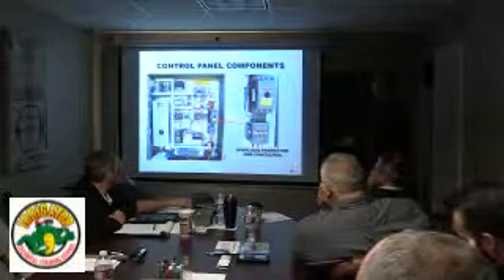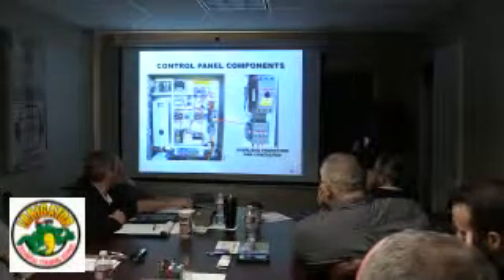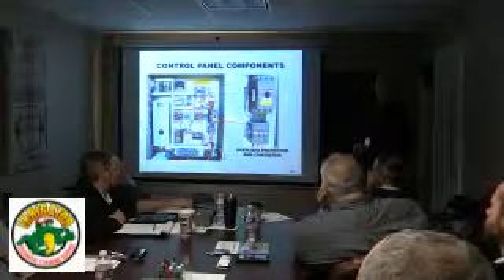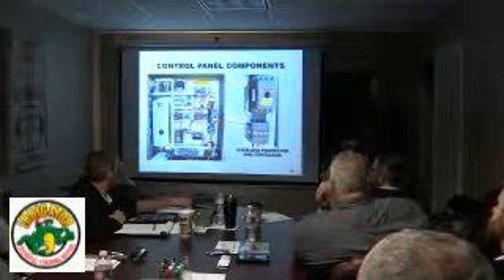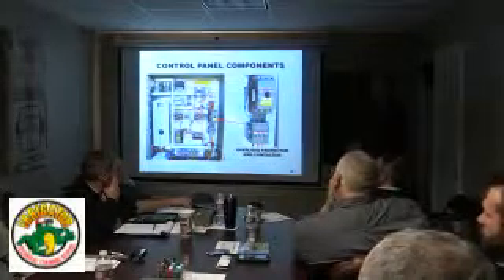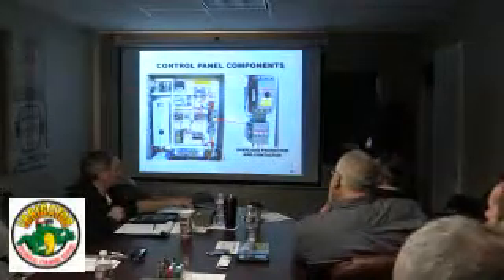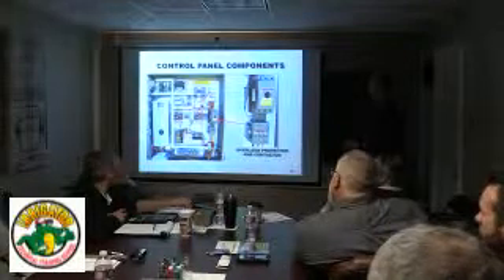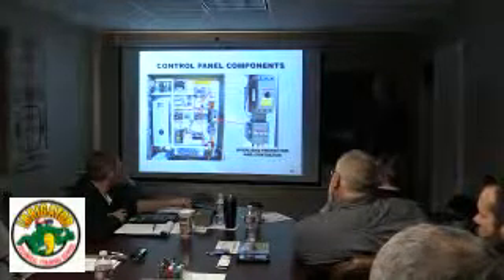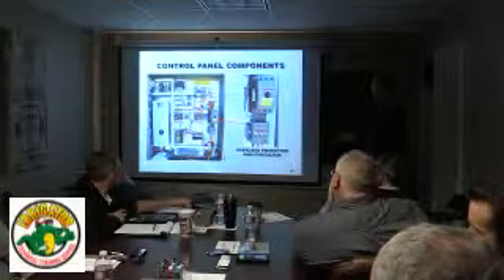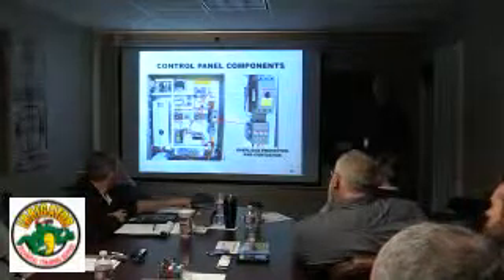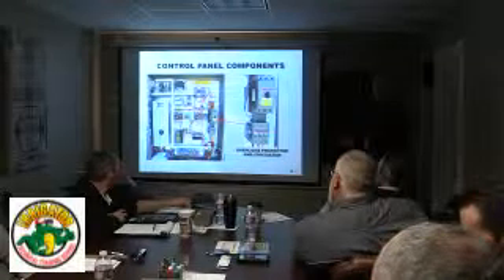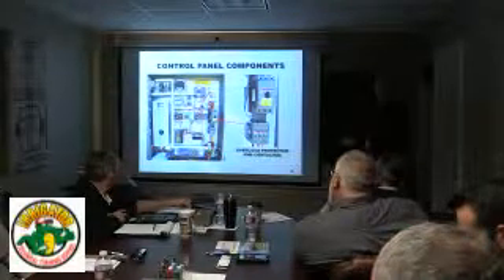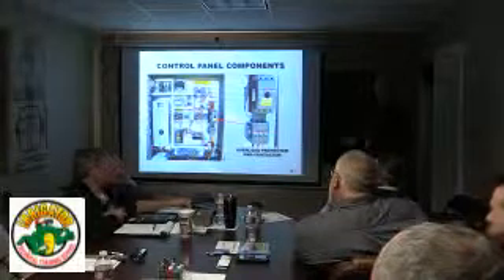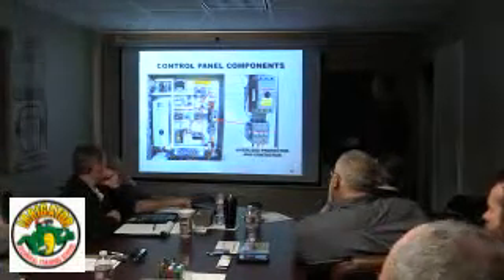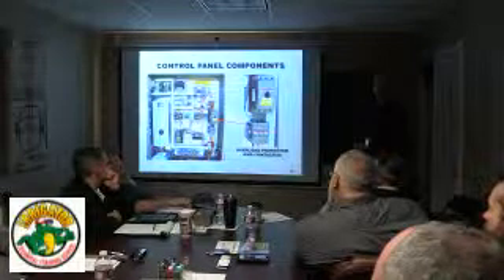The main reason for this contactor is to protect the drive in case of over voltage or under voltage. The motor saver, or this voltage monitor right here, sends a signal to the PLC saying that the voltage is okay, everything is fine. The PLC will then output on its output, energize the coil on this, and pull this contactor in, and that will power up the drive. So if the voltage monitor senses imbalance, phase imbalance, or loss of phase, or low voltage, the PLC is going to disengage this contactor, and it's going to pull the power from the drive.